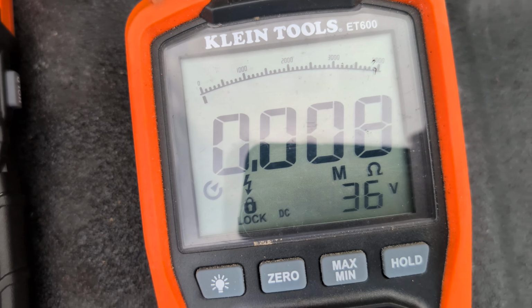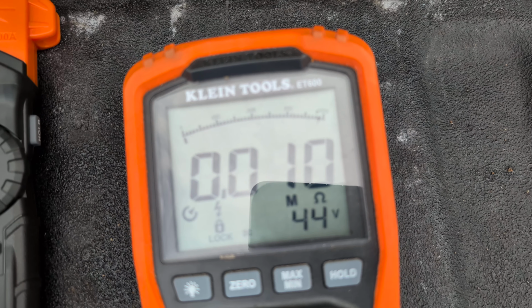That's where it is. That's why you need a Megger to trace a ground fault in a circuit, and that's why a regular ohm meter doesn't work for this type of ground fault that's caused from moisture and so forth. This will work great for a dead fault if you wired it wrong, but it won't find faults like this. You need a megohm meter and set it to 125 volts to trace that fault through the circuit.